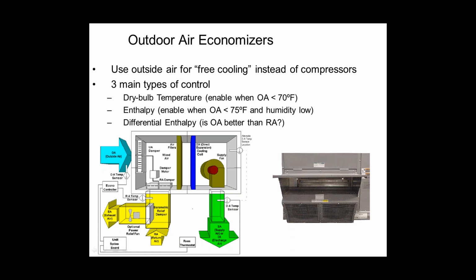So for you guys that do field work, by code, you're required to set all the economizer changeovers for 70 degrees. If you're still doing it for 55, you are woefully out of compliance for this code and for the previous versions of the code. The second way you could do it would be enthalpy, right? For those of you that don't know what enthalpy is, don't even use the word enthalpy. Just think of temperature and humidity. We're going to check both things, and if one of those things is quote-unquote bad, we're not bringing the outside air in. So if you do an enthalpy-controlled economizer, instead of a 70-degree set point, the code will require a 75-degree set point, right? A little more aggressive.